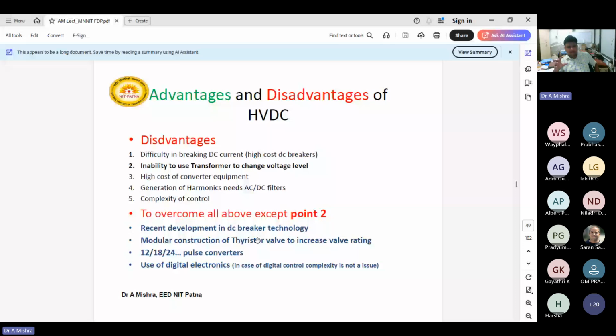As compared to an AC breaker, DC breaker cost is more. You will find that because you are already in the area of the power system. If you try to find out the cost of, suppose, the same rating, 500 ampere or 1000 ampere, AC breaker cost and DC breaker cost, the DC breaker cost will be high. So that is one problem. If you are going for the transmission, definitely you will be bound to use DC breakers. Second point, inability to use the transformer to change the voltage level.